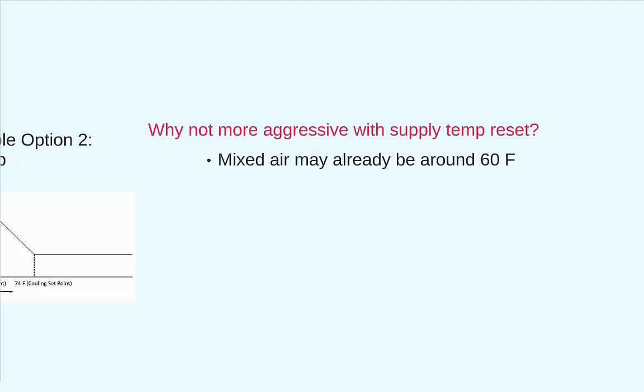Imagine the return air temperature is at around 71 degrees Fahrenheit, and the outdoor air temperature is at 49 degrees Fahrenheit. And for this example, to meet the ventilation requirements, let's assume we need to bring in 50% outdoor air. The mixed air temperature entering the air handling unit would end up being around 60 degrees Fahrenheit. So again, it's not like we purposely wanted to bring that temperature down. We just had to in order to meet ventilation requirements.